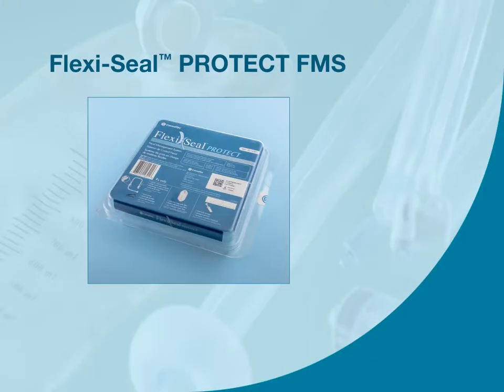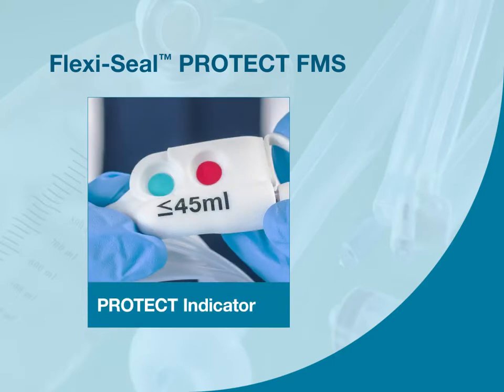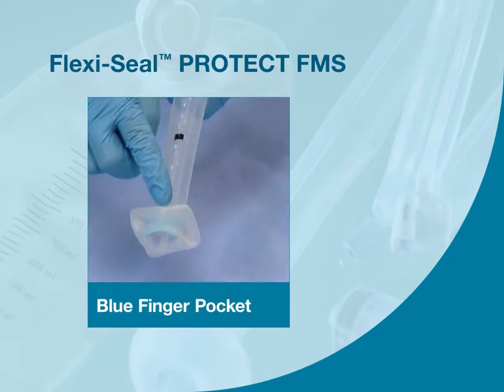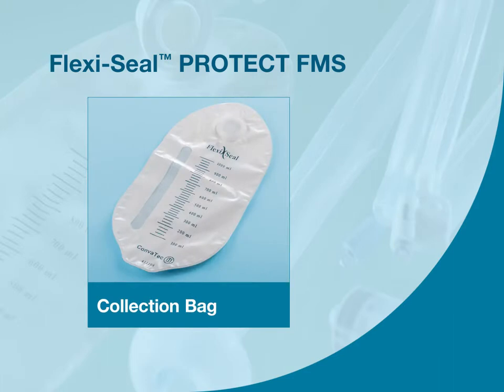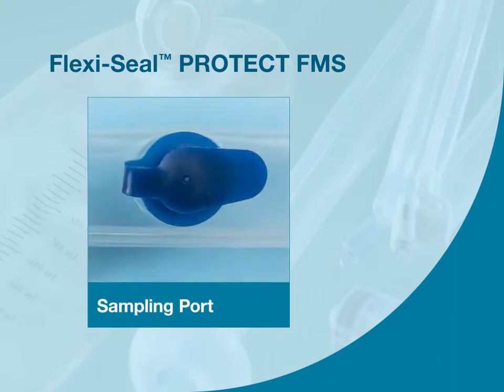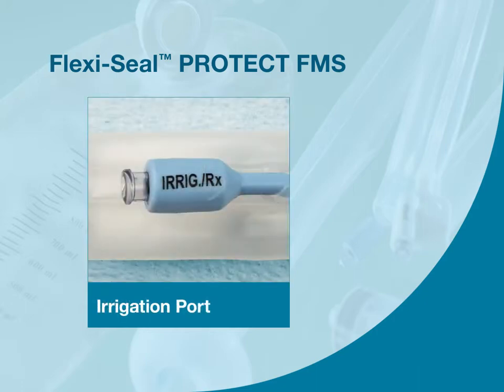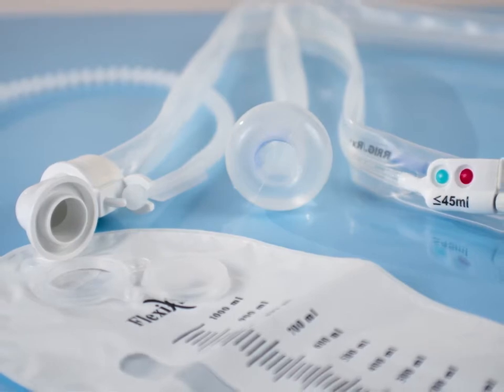The Flexi-Seal Protect Fecal Management System includes the following components. 1. The Protect Indicator, which provides visual indication to help prevent overfilling and helps indicate optimal fill. 2. Soft retention balloon with catheter. 3. Patented blue finger pocket for ease of insertion. 4. Privacy collection bag. 5. Sampling port provides access to the catheter for safe and easy stool collection. 6. White cap to prevent the risk of misconnection between the blue IRRIG/RX port and the white inflation port. And 7. The blue port marked IRRIG/RX. We'll discuss each of these features throughout the course of this video.